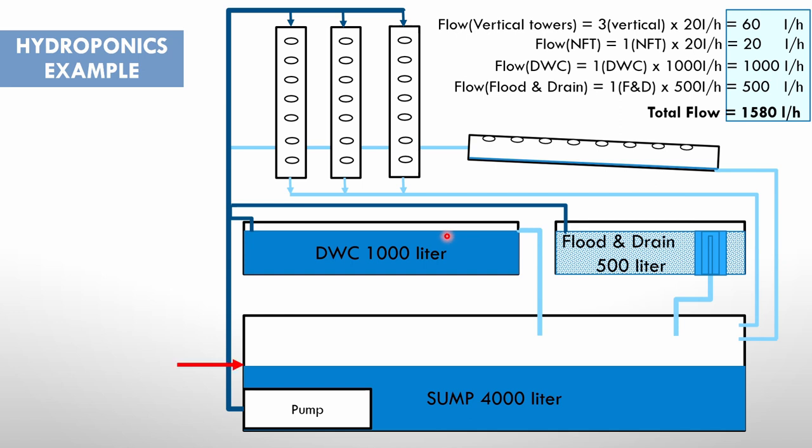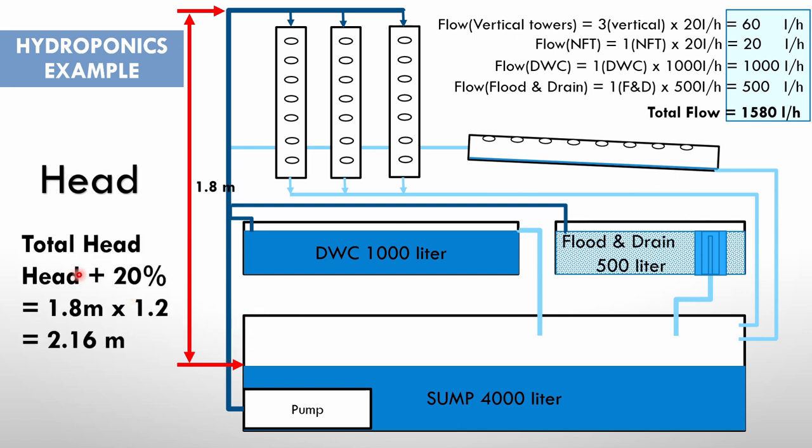Our head is calculated only once for the system, from the lowest point in the sump till the highest point where you lift your water. That will give us our head. In this case, 1.8 meters. Please remember that head is only calculated from the lowest to the highest point, and you don't consider anything in between. So that's our head. We've said we must compensate for friction in the pipes, and I do that by adding 20 percent to my head. So if the head is 1.8 meters, I multiply that by 1.2 to add that 20 percent. So my total head in this case is 2.16 meters.